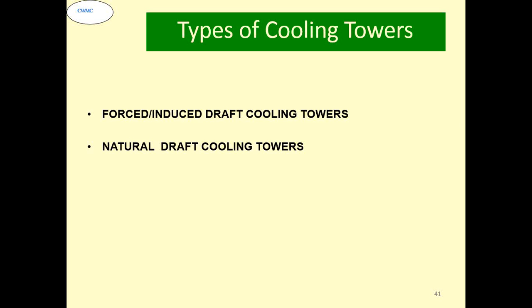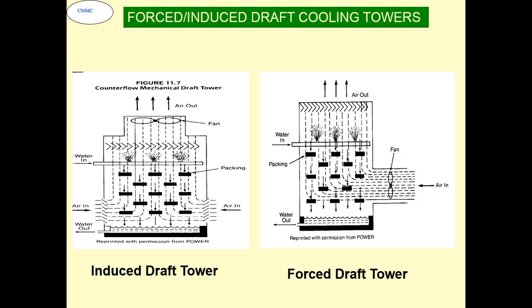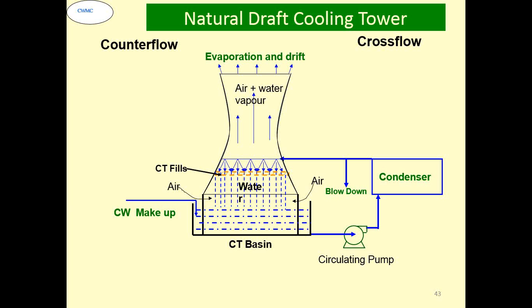Now, different kinds of towers encountered in the industry are the forced or induced draft cooling towers or natural draft cooling towers. In an induced draft or forced draft cooling tower, there are fans, and the air is induced or forced through to cool the dropping liquid. In the natural draft, either counterflow or crossflow, there is natural movement of the air which cools down the hot water, and then it is sent back to the basin and then back to the system. Normally these have hyperbolic structures.